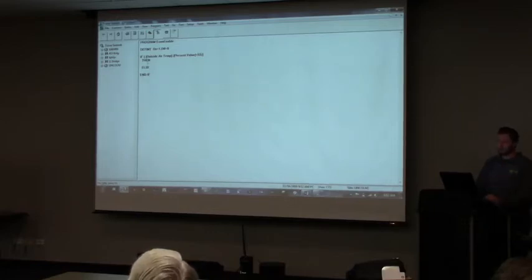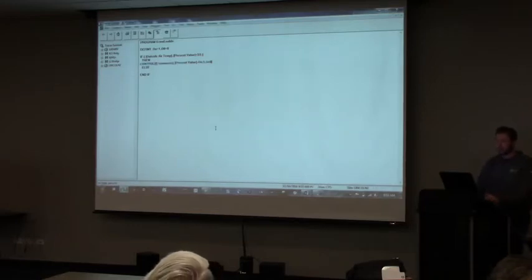So all I have to do is select right down here, and then I can hit Edit, add statement, and I want it to control on if that's true. So I'm gonna hit control, and then hit OK, and then select my points. So binary output, they have the economizer, and I'm just gonna hit OK, and it's gonna ask you, what do you want to control this to if that's true? And I'm just gonna put on, and I'm gonna hit OK.